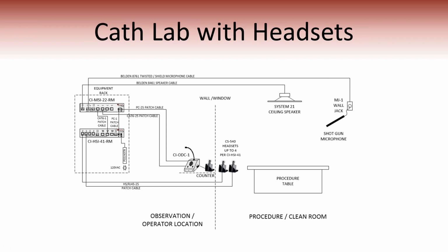In this case, you've got one headset plugged into the operator desk console, but then they wanted a couple more over here in the operating room. So we put the charging bases in the operating room because this sometimes is lead shielded and you need to get those receiving units inside of that operating room. You simply take headset cables over to your headset interface.